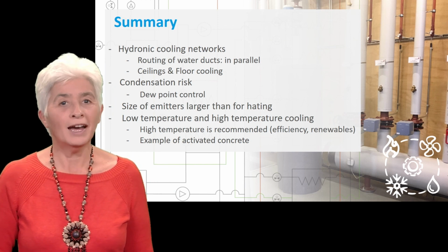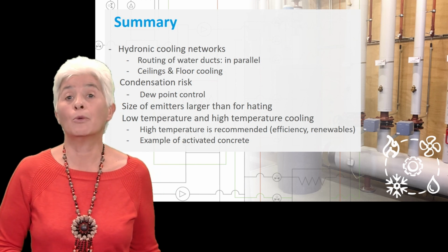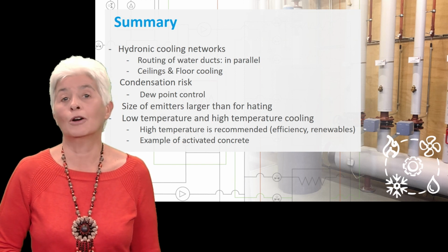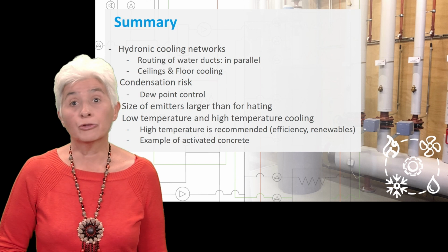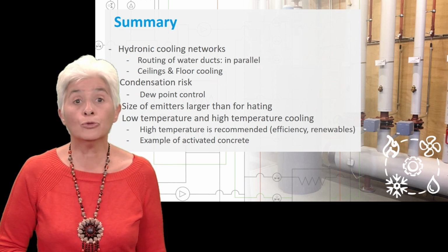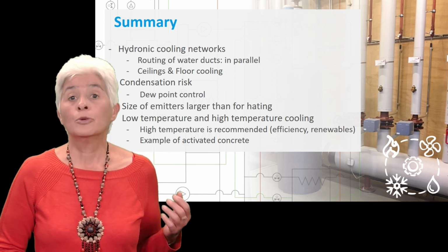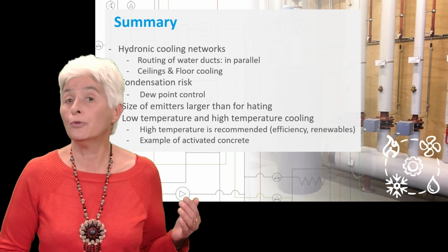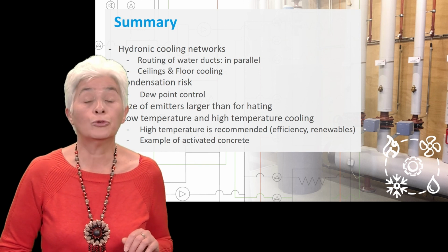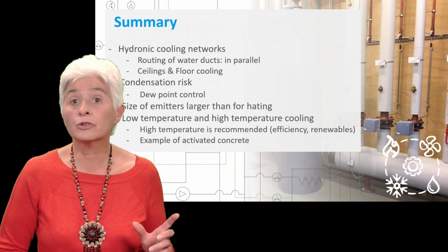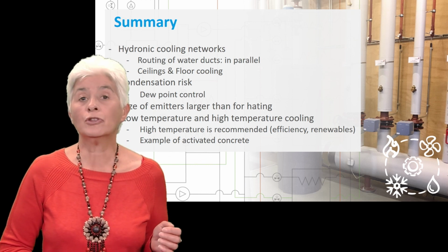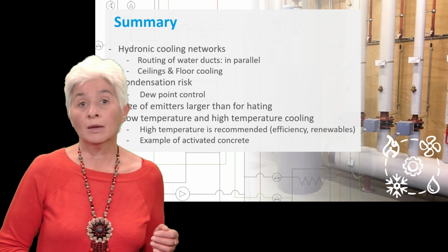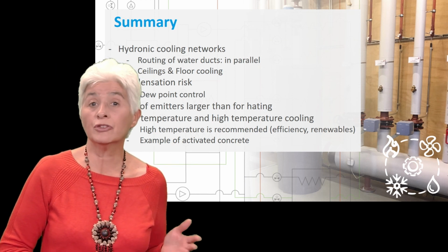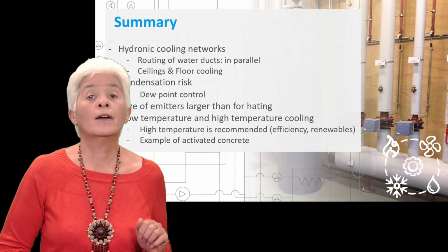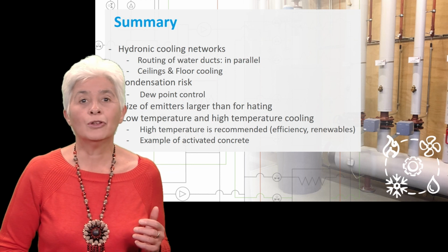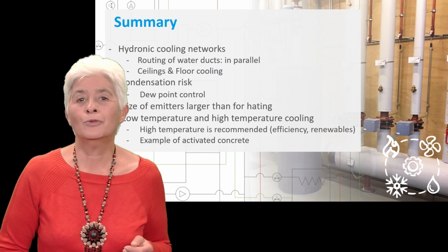In this lecture, we studied hydronic cooling systems, which are room systems cooled by water. Just like for heating systems, the routing of the networks must be in parallel. Radiators are not used in general as their surface area is too small to produce the needed cooling capacity. The preference is to cooling ceilings and sometimes floor cooling. Much attention must be brought to the condensation problem, and dew point control is a must. We studied the advantages and disadvantages of low temperature and high temperature cooling. High temperature cooling systems allow for higher efficiency chillers and the use of natural cold resources. Finally, we went into a specific application, which is activated concrete.